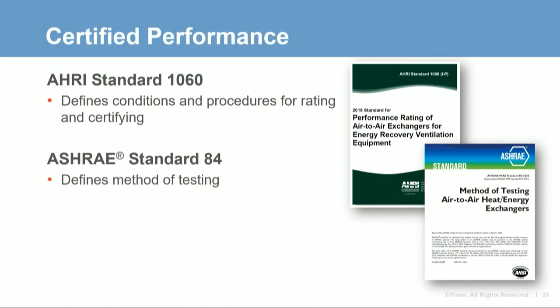Before Eric introduces the various technologies for air-to-air energy recovery, let's talk briefly about testing and rating these devices. AHRI Standard 1060 defines the conditions and procedures for rating and certifying the performance of an air-to-air heat exchanger, while ASHRAE Standard 84 describes the method of testing. These standards introduce the term effectiveness, which indicates how well this type of device transfers energy.